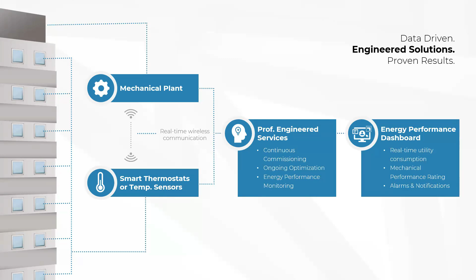So, a little bit more detail here, getting into this phase one: what are these smart controls doing for this building? Boiler loop temperatures are absolutely critical, right? One of the biggest mistakes we all make in the industry is that we put condensing boilers in and then we don't operate them at low temperatures. Therefore, they never condense, and their efficiency never approaches the rated efficiency.